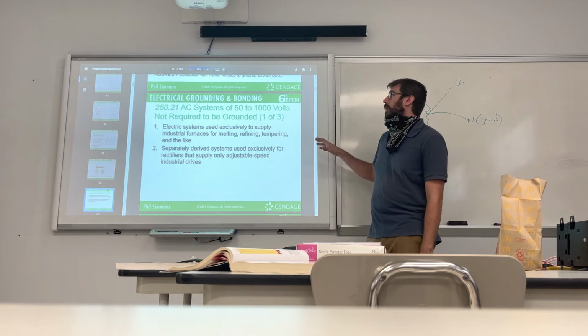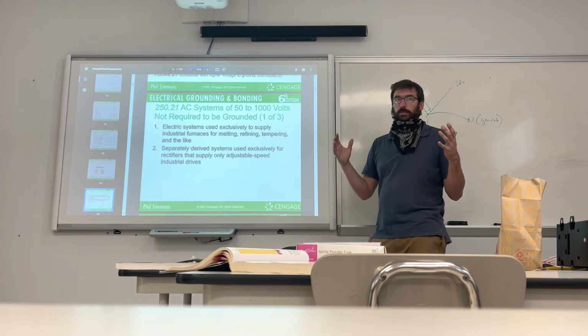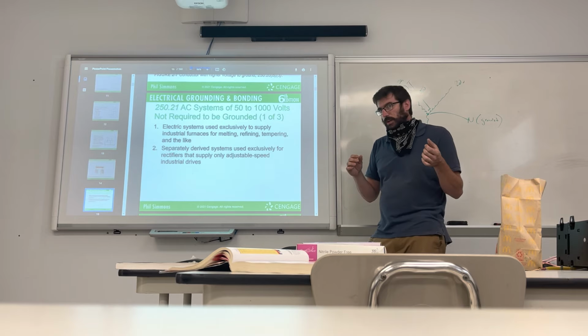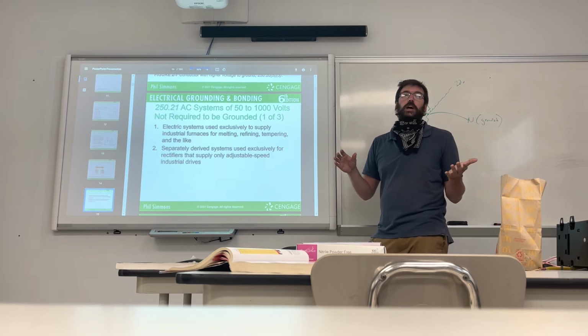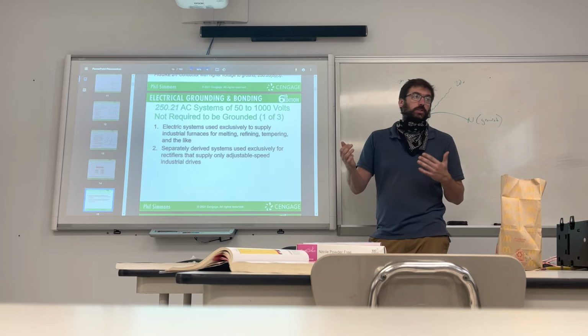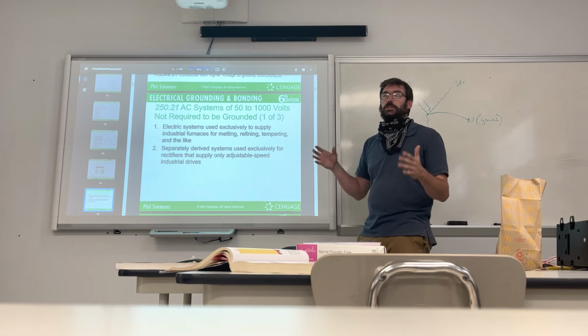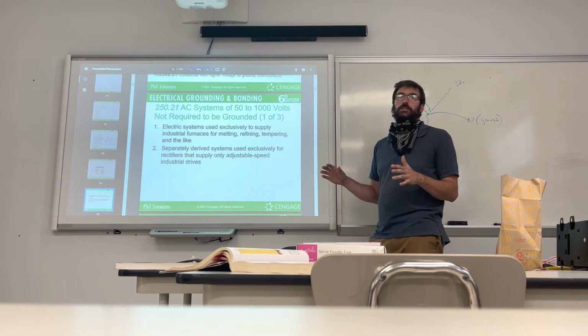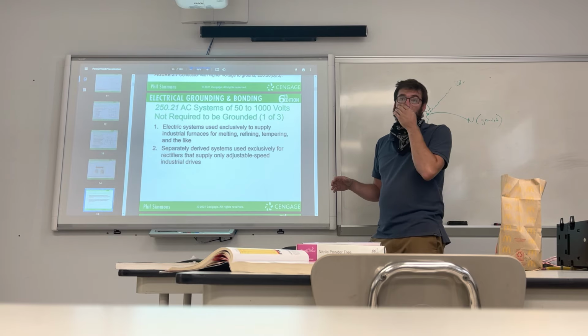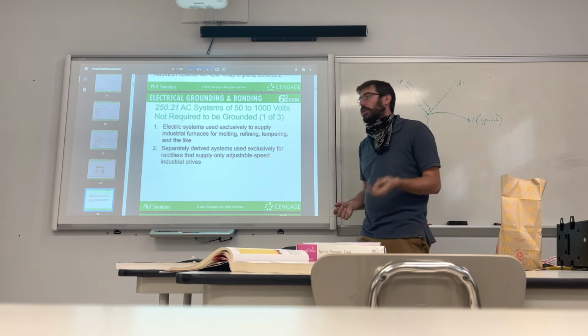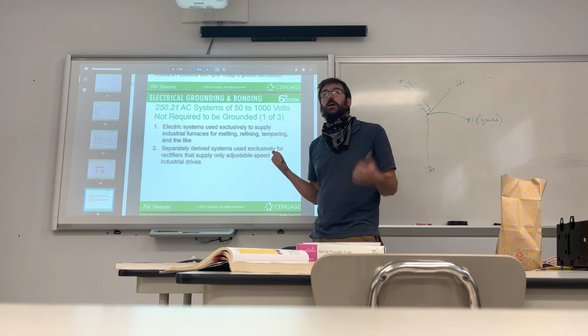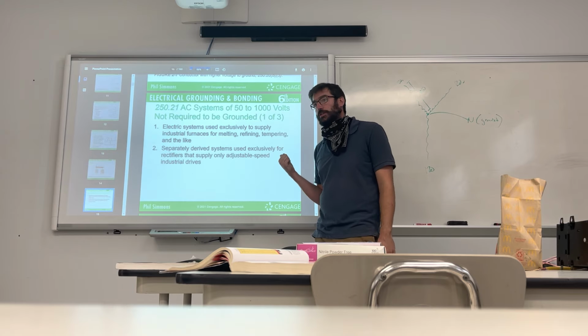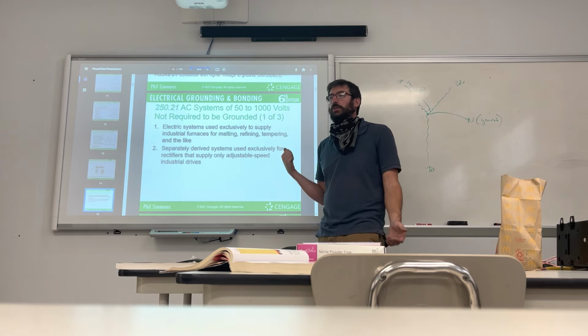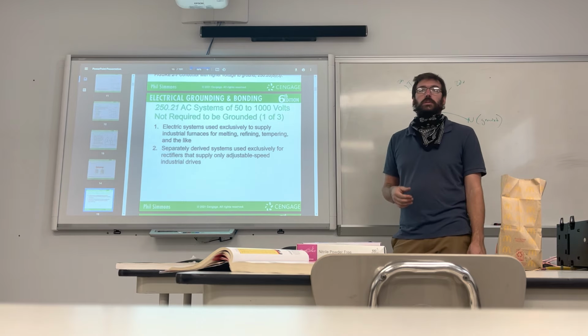Those are the ones that are not required to be grounded, because in reality, they can actually run full time. If one leg goes bad, something grounds out, that system can still run, because it would be more detrimental if the system wasn't running. You know, like a lot of people could be without water. Let's say that's a pumping station that's supplying all Scranton with water. Do you want that thing to fail halfway through the day? Absolutely not. You might want that to be an ungrounded system.